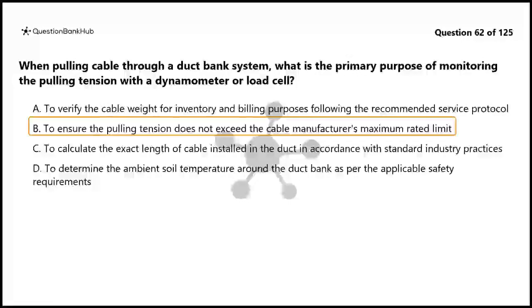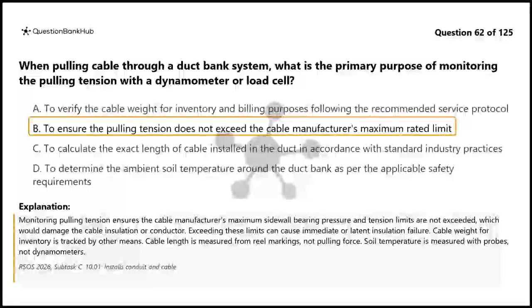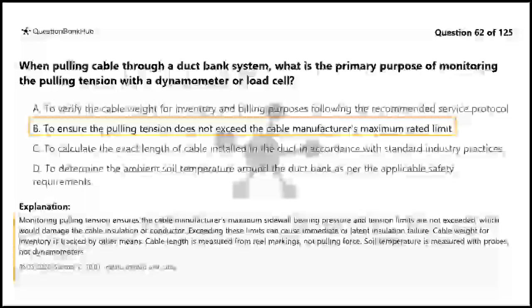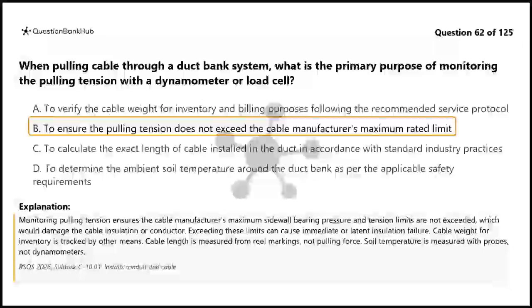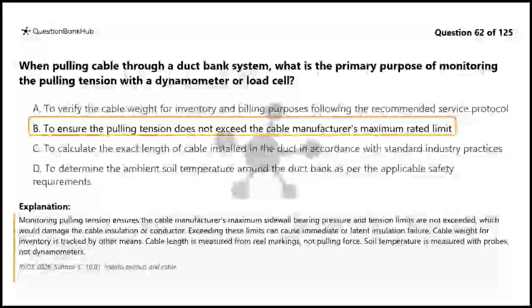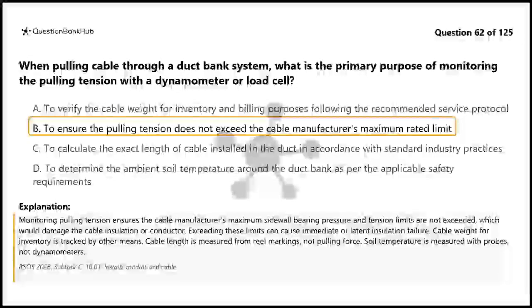The correct answer is B. Monitoring pulling tension ensures the cable manufacturer's maximum sidewall bearing pressure and tension limits are not exceeded, which would damage the cable insulation or conductor. Exceeding these limits can cause immediate or latent insulation failure. Cable weight for inventory is tracked by other means. Cable length is measured from reel markings, not pulling force. Soil temperature is measured with probes, not dynamometers.